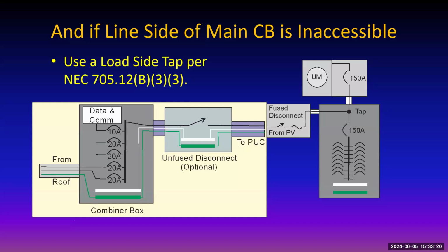If the loads on that panel don't require all that PV current, then it can go up to that circuit breaker on top. But you can't have more than 150 amps going out either. But that's not a big deal because the PV itself only has 40 amps maximum that's going to go out. So when we're backfeeding to the utility, it's not a big issue anyway. So you could actually have a couple of circuits between those two. And as long as the sum total of the overcurrent protection for the loads plus the source does not exceed the rating of the bus bar, then you're okay. And that doesn't include the rating of the 150 amp.